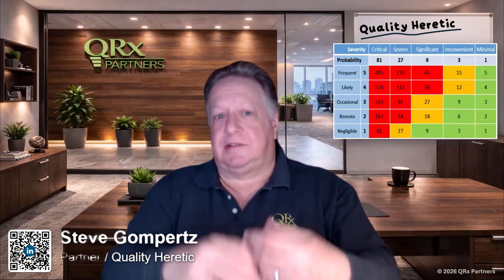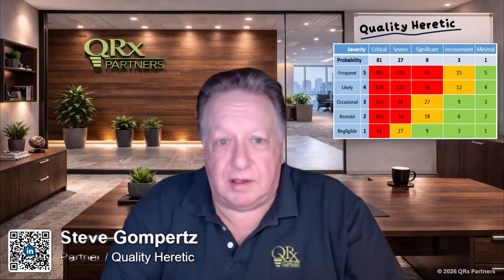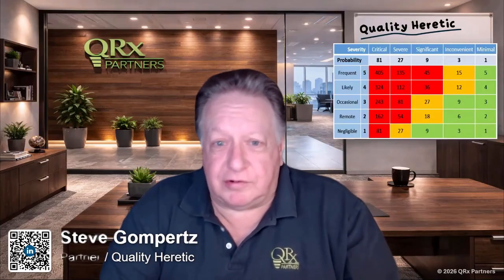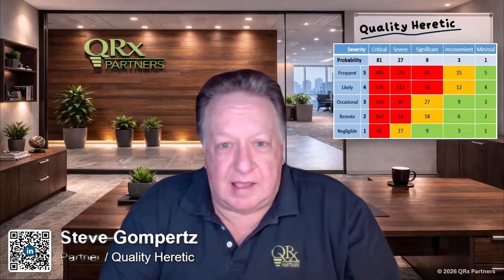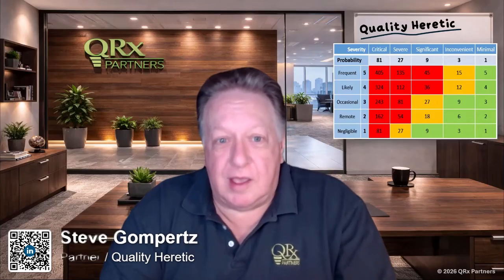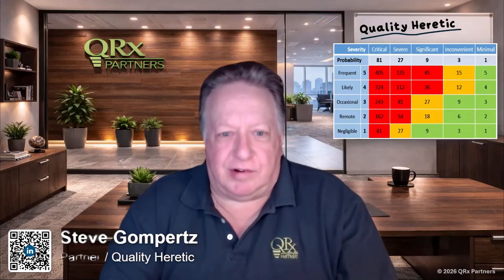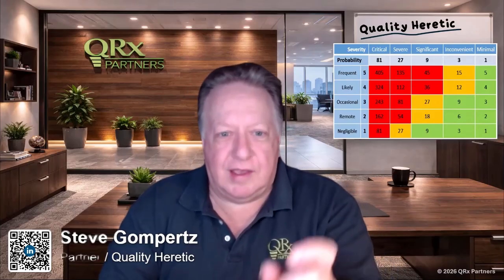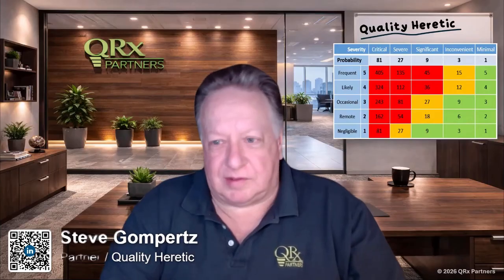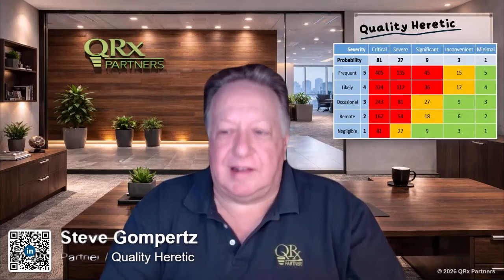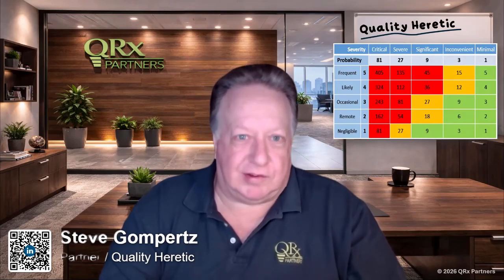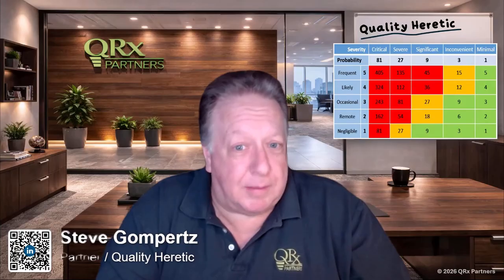And so now, if you put that into that matrix, you get a very different look at your risk levels and your risk criticality, right? And notice that the zones have changed, right? It makes you rethink your zones. But now, at those two corners that I talked about, right, there's clear differentiation. Something that involves death is definitely differentiated from something that's just more annoying, right? Regardless of the probabilities, right? And that's the point, is that it gives severity sort of an override capability.